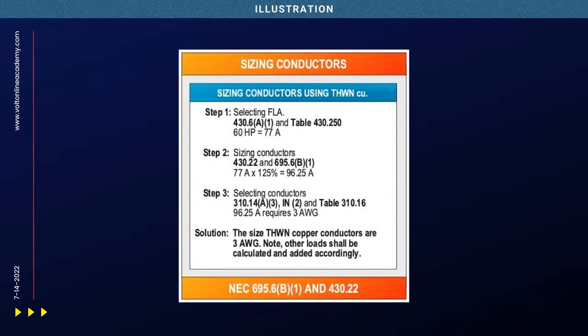But if you take 77 amps at 125%, that's going to give you 96.25 amps. And then all I'm going to do is look at Table 310.16. In this case, we're going to say they're 75 degree C terminals. And the next size above that for the amperage is 100 amps, which is a number 3 conductor.